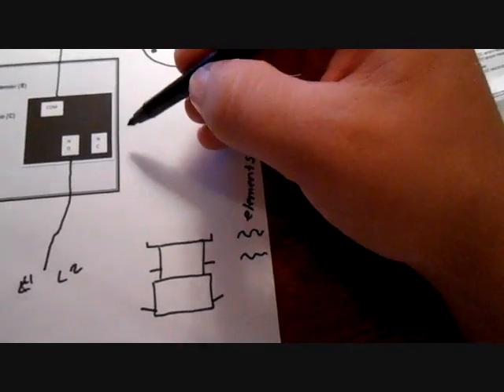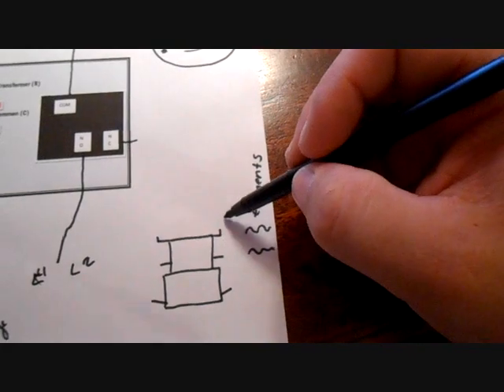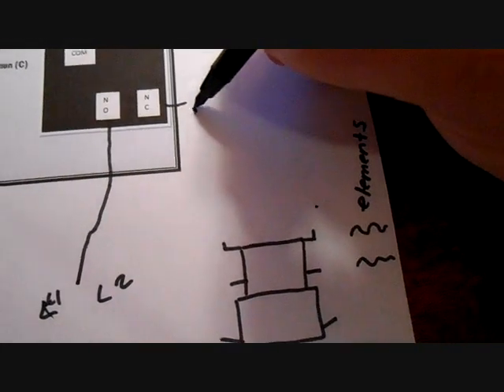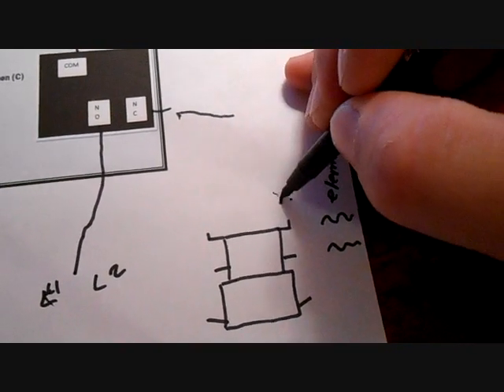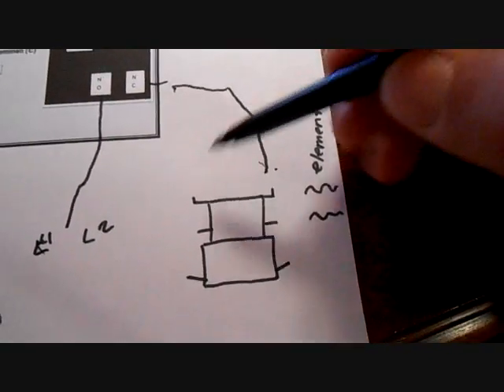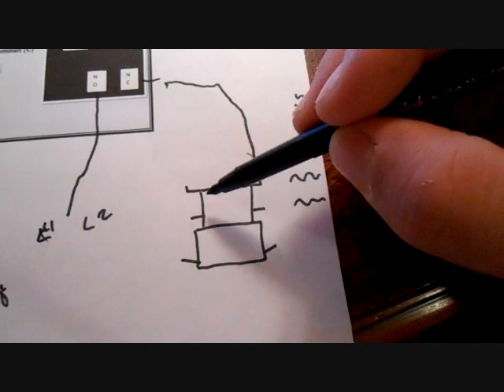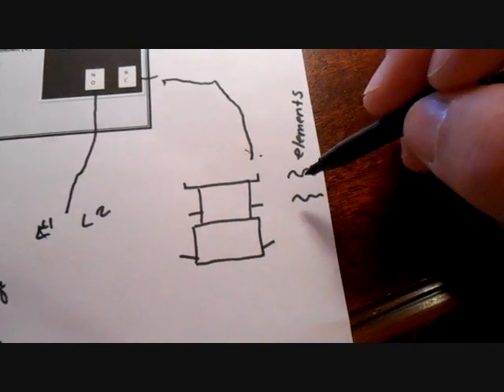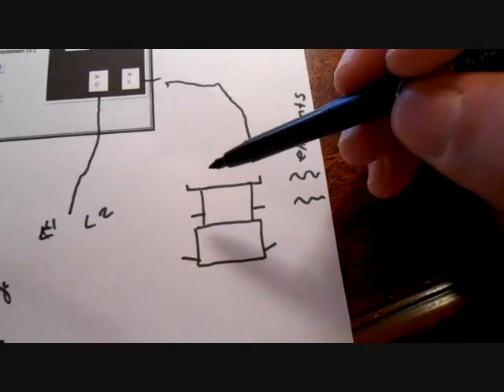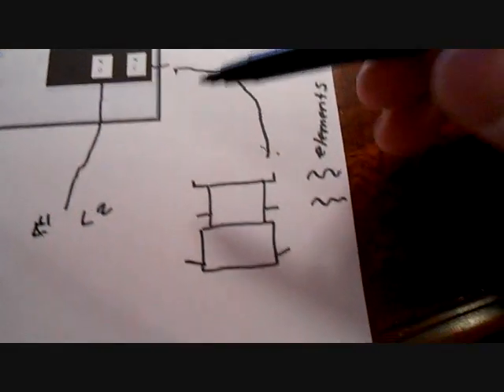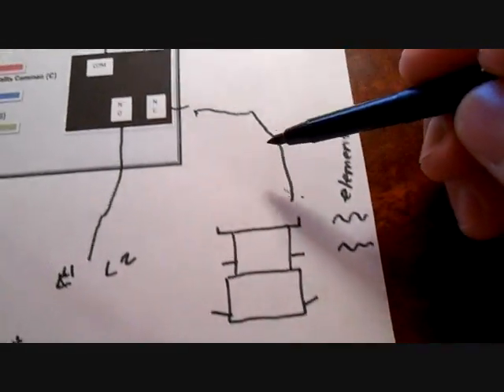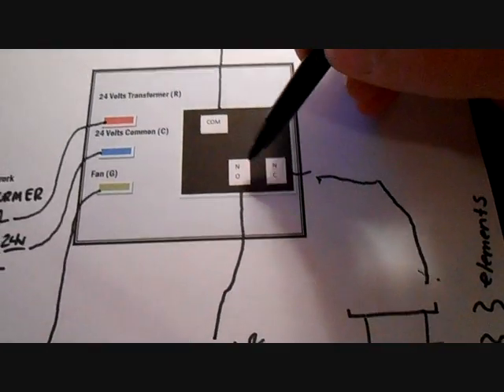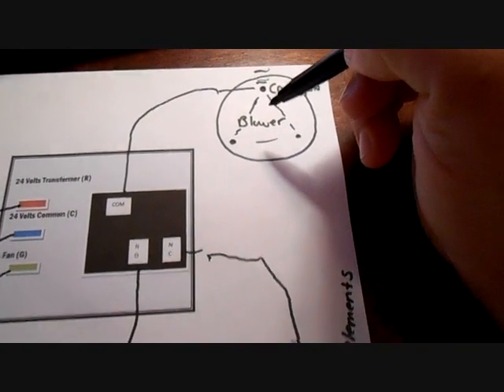And then the last one will be our normally closed. And it will run to the other side. Let's see if I can get my paper to sit still. It will run to the other side of the sequencer, basically the side of the sequencer facing the elements. You have your power coming into the sequencer here. And when it makes, power flows into the heating elements and you'll have your supplementary heat. And by that same token, if the blower relay is off and the power is passing through the sequencer, it will also pass around through to the normally closed terminal, pass around to the common, and turn the blower on. That's how that works.